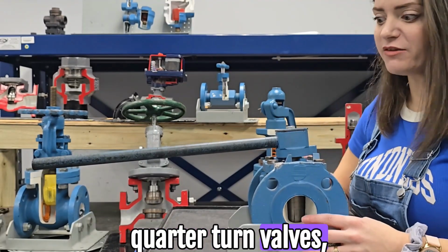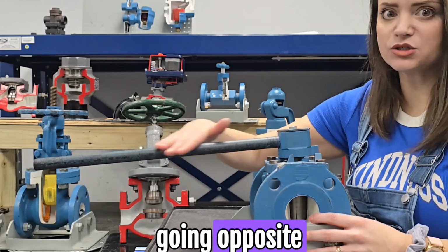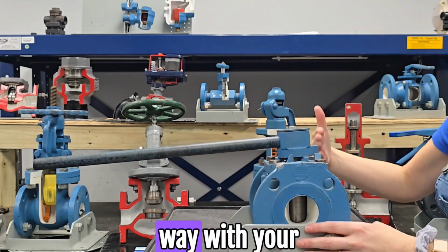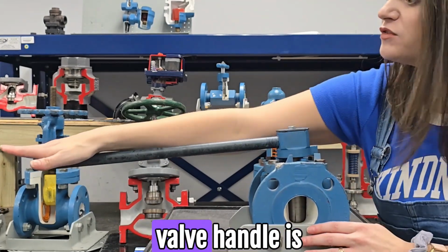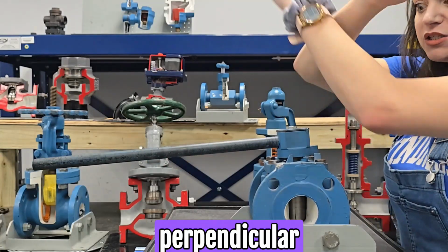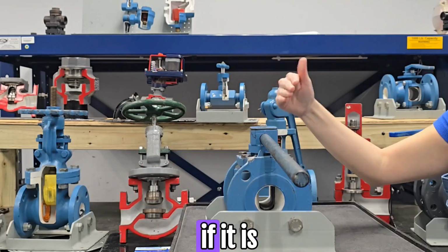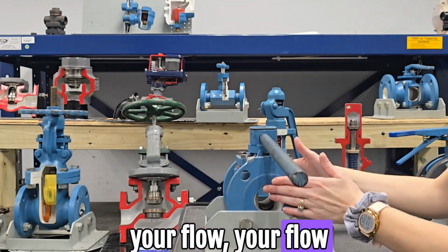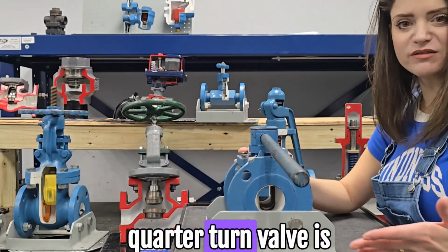Another thing with quarter turn valves, if the valve handle is going in the opposite direction of the flow, so your flow would be going this way with your flanges, right? The valve handle is perpendicular instead of parallel, that means it's closed. If it is parallel with your flow going here, right? That means the quarter turn valve is open.